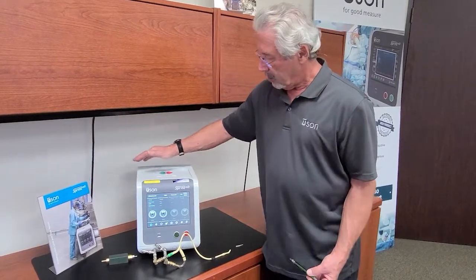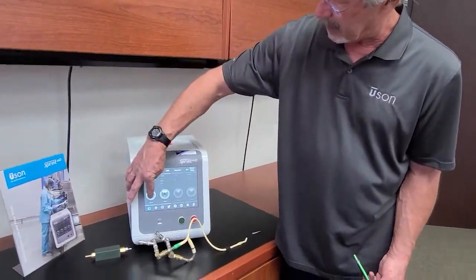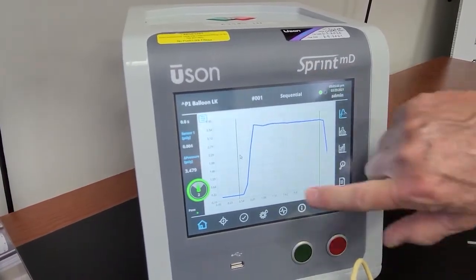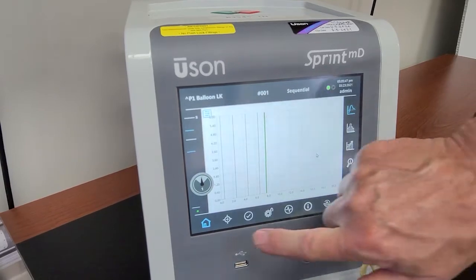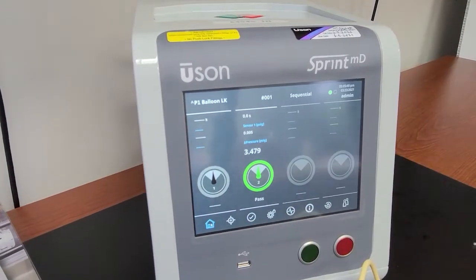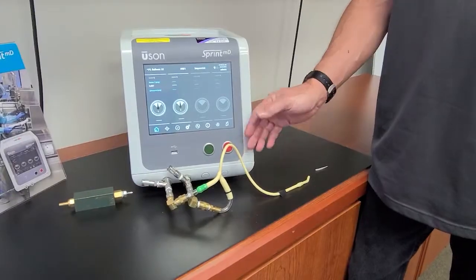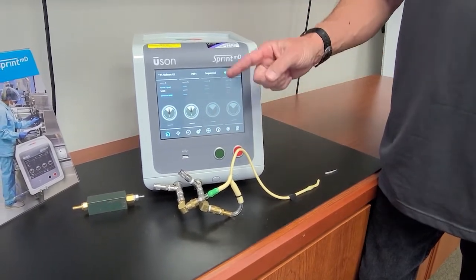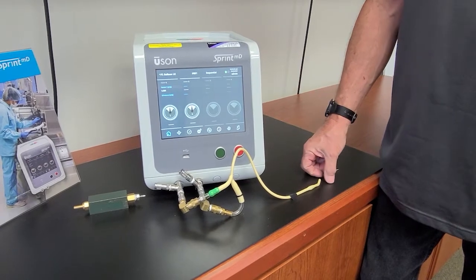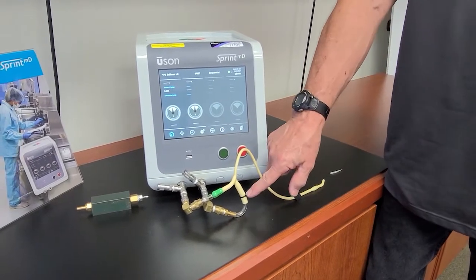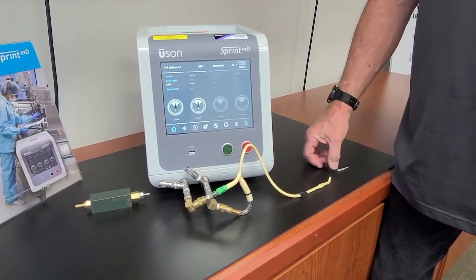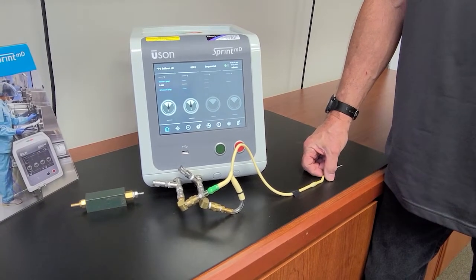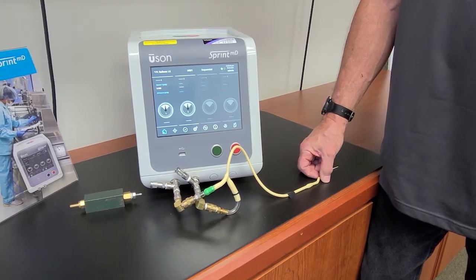I have my Sprint MD tester, which has a touch screen and also has a slide feature that allows you to slide through the different run menus. I have for my test port today a catheter which has two test ports. We will be performing leak tests on the balloon port on channel one, and we'll be performing leak, back pressure flow, and occlusion tests on port two using programs three and four.